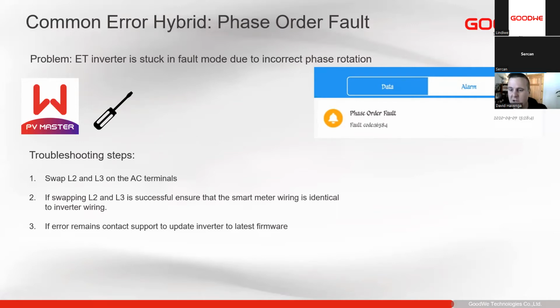So when we install it and connect the grid, we might see the inverter just stays in fault. In PV Master, we can see the alarm for phase order fault. Then we simply swap phase 2 and 3 around, restart the inverter, and see that the phase order fault is cleared.